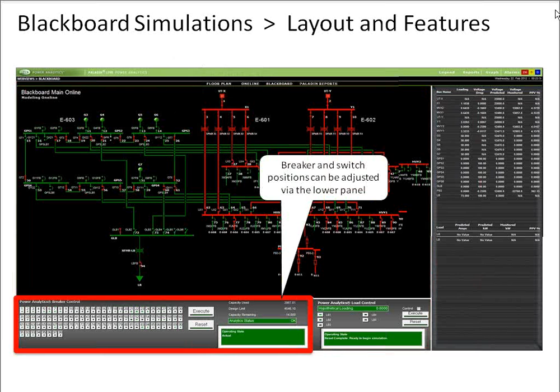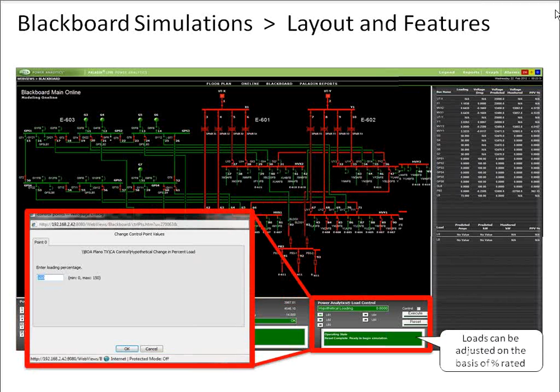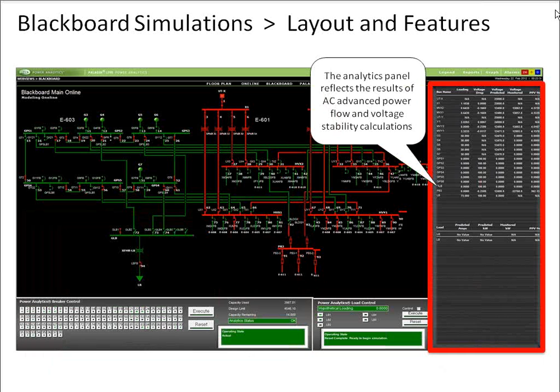You can open breaker and switch positions on the lower panel, and adjust load amounts based on another panel. Once the operator reconfigures things, adjusts loads and sources, it runs a load flow study, and the results come up on the side panel.